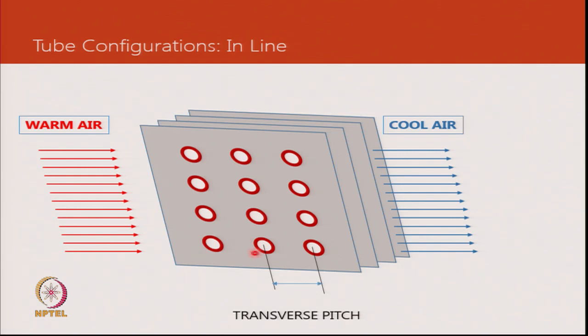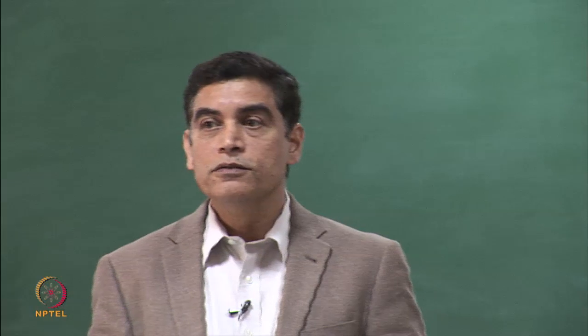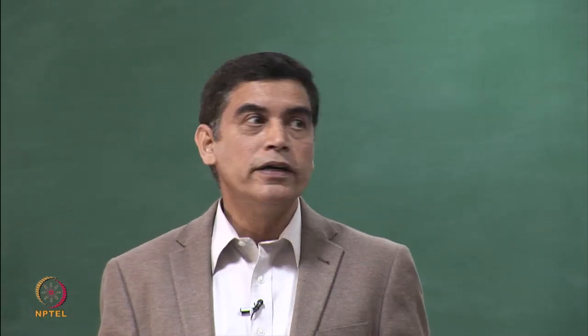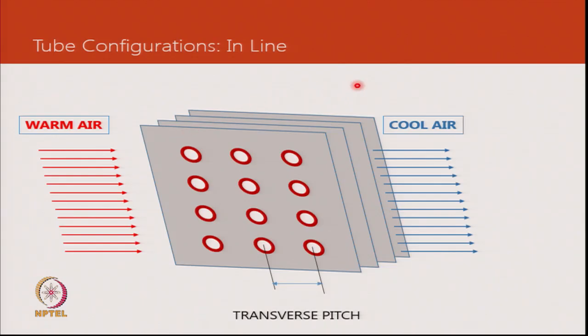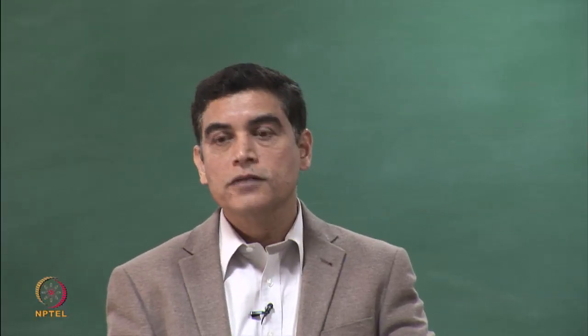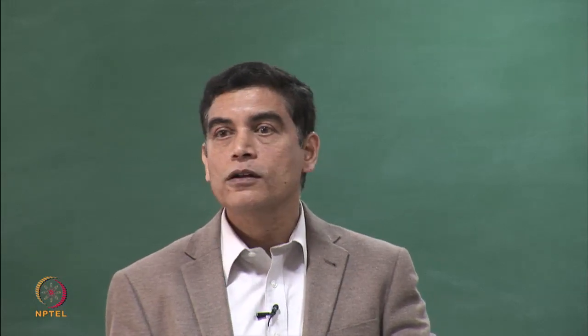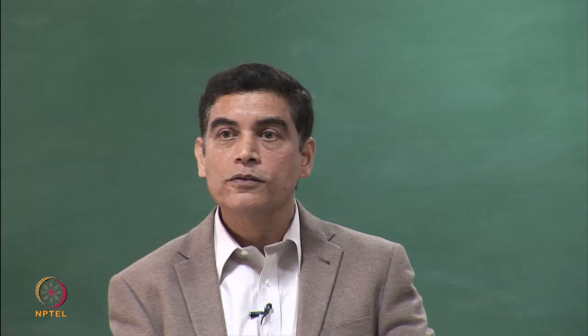To keep an eye on costs, the length of copper or aluminium tubing is one key variable. When looking at face area, we define the finned area dimensions — the length of the finned area and the height corresponding to the number of tubes in the air flow path. For a window air conditioner example delivering 5 kilowatts, you could have about half a meter of coil width and around 16 tubes vertically, with a vertical pitch of 1 inch (25.4 mm) and a tube diameter of 3/8 inch.